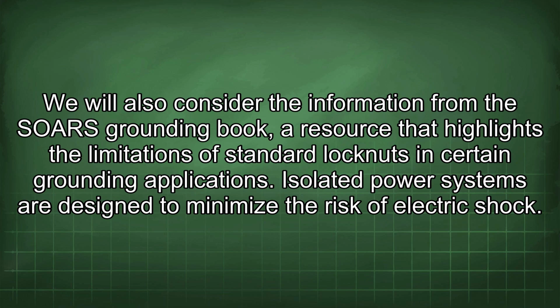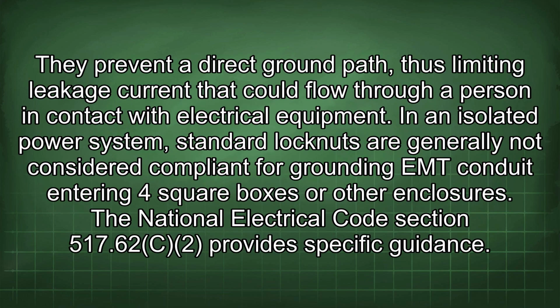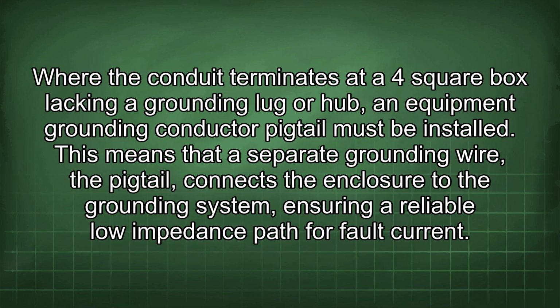Isolated power systems are designed to minimize the risk of electric shock. They prevent direct ground path, thus limiting leakage current that could flow through a person in contact with electrical equipment. In an isolated power system, standard locknuts are generally not considered compliant for grounding EMT conduit entering 4 square boxes or other enclosures. The National Electrical Code Section 517.62C2 provides specific guidance. Where the conduit terminates at a 4 square box lacking a grounding lug or hub, an equipment grounding conductor pigtail must be installed. This means that a separate grounding wire, the pigtail, connects the enclosure to the grounding system, ensuring a reliable low impedance path for fault current.